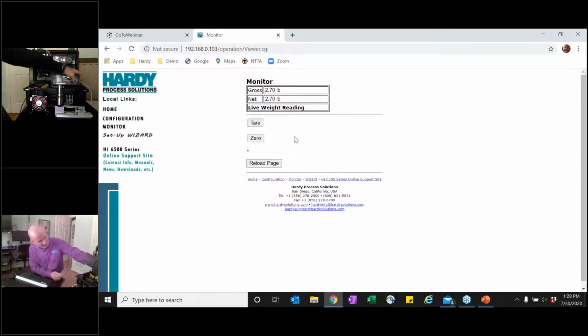So now we'll go in. We'll do the high cal. And now it thinks it's 5 pounds. So we've got 5 pounds there when it's actually 1.45 pounds here. So now we'll take the weight off. You can see with no weight on the scale, it's saying that we have a 1/4 pound. When we put 1 pound back on the weight on the scale, it says 3.55 pounds.